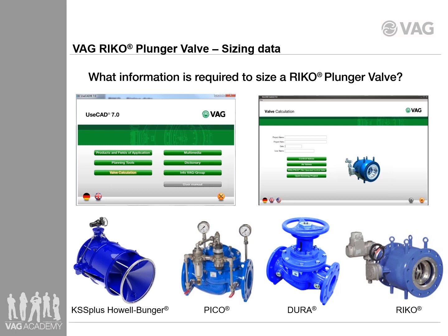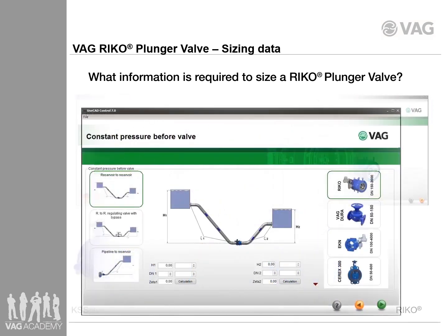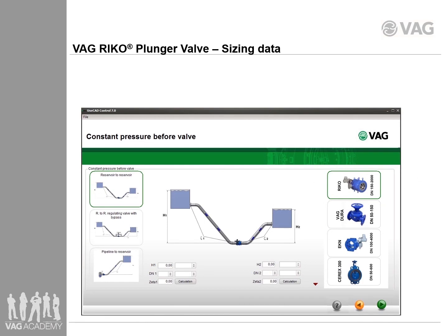In the case of the RIKO plunger valve, VAG uses the software to select the proper valve diameter and control cylinder and to evaluate hydraulically critical installations. The results of the calculation depend on the realistic representation of the pipeline system. VAG will not assume any liability for the correctness of the calculation. The results do not replace the pressure surge calculation for the network of the customer.